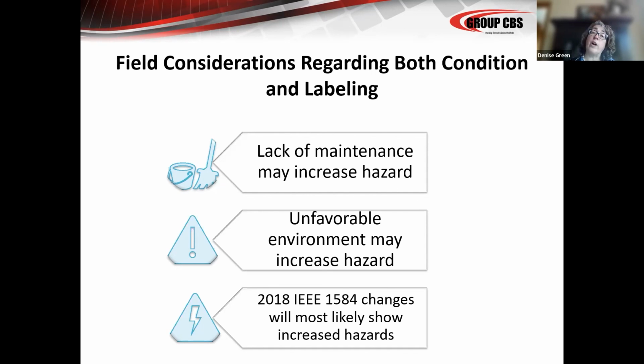So that's also a very important thing to remember: that 25 calorie suit they're telling you to wear is just going to make sure you don't have more than a second-degree burn. Okay. And then remember that anything over 12 to 15 calories, you have the potential of impact injury, if the equipment starts to disintegrate.